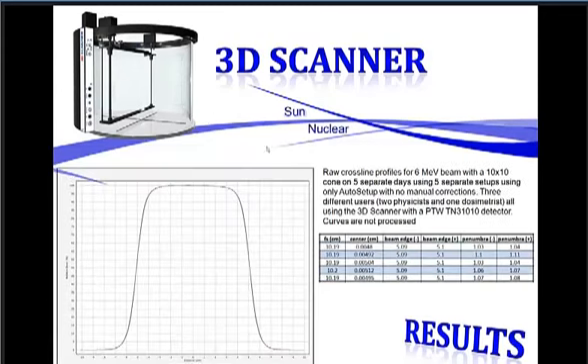When we're doing commissioning, we also like to look at the cross line profiles, whether the inline and cross line are matching up, whether or not when you center the tank. For those of you who center with the Blue Phantom or the PTW phantoms that I'm familiar with, it's sensitive to how you're doing that. So we looked at the cross line scans, same thing. We had the same physicists and dosimetrists running the 3D scanner with auto setup and then ran cross line profiles. Those are the statistics there as far as the five separate runs under five separate setups during commissioning of the Novalis TX. It's pretty much spot on. These are all unprocessed curves. So this is exactly what they saw the day they scanned. It was a relatively consistent setup.